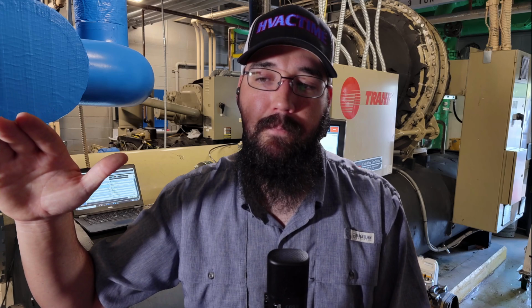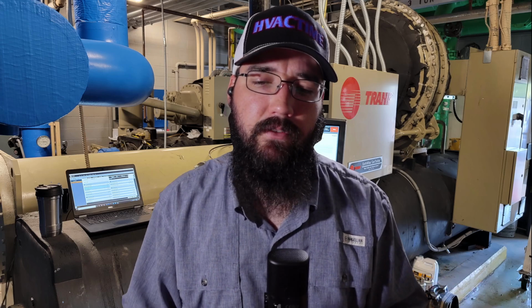It simplified the process. Yeah, now we've got a controller and such in the way, but my point being, even with a lot of your older machines, many of them may not have shipped with EXVs from the factory. It may be a retrofit package that we did at a later point because of whatever reasons. But yeah, all the way down to your smallest scrolls, or scroll air cooled at this point, they will have EXVs most of the time. When you factor in just the efficiency side of it, there's not very many people that I'm aware of that are still trying to utilize TXV technology for these systems.